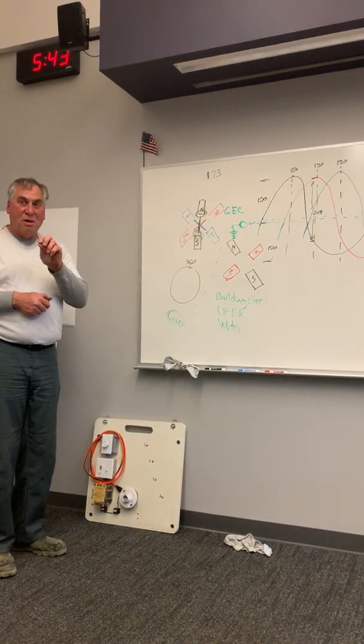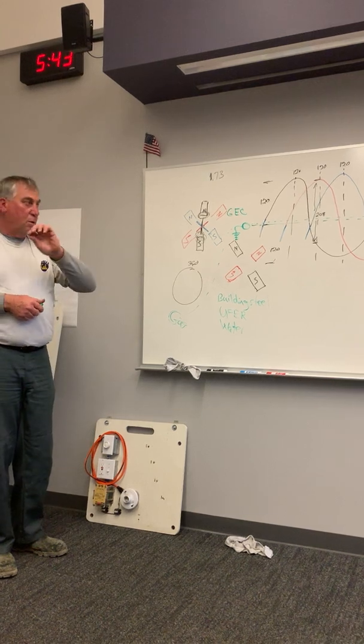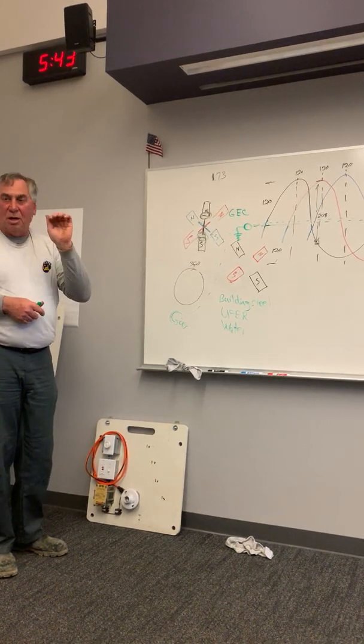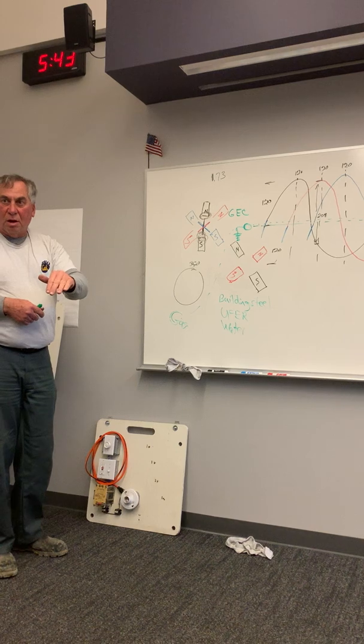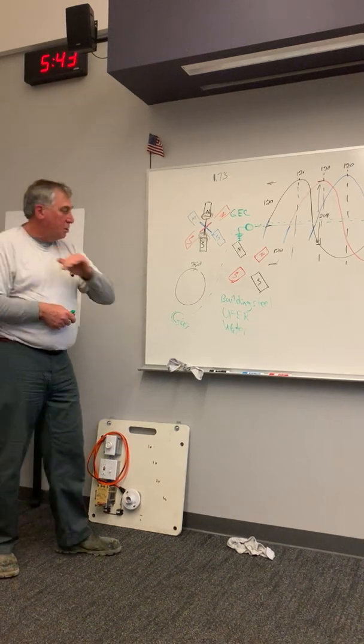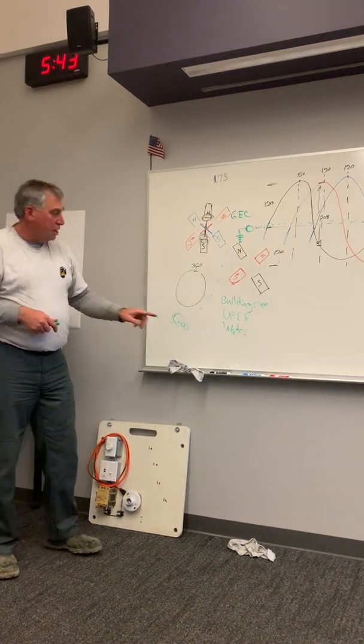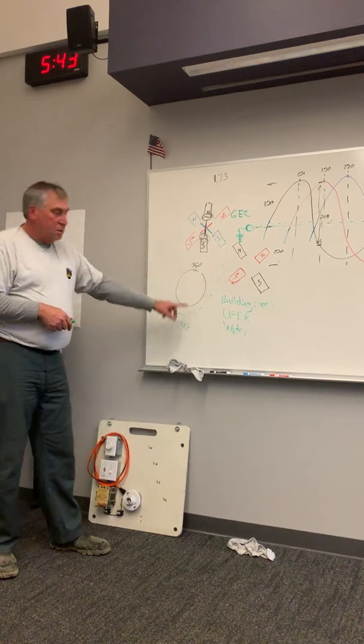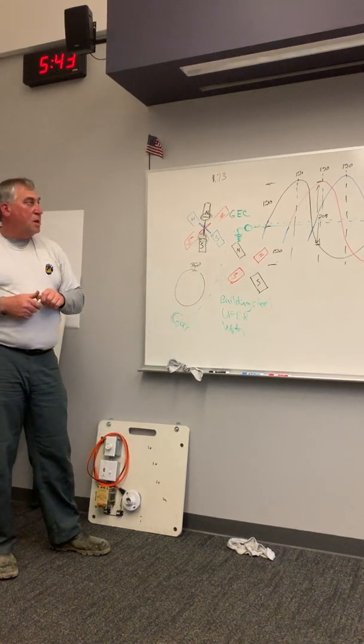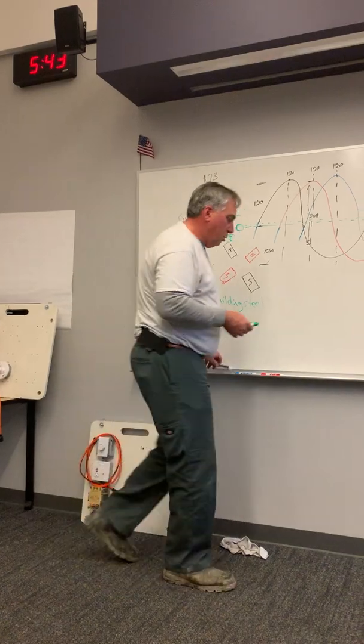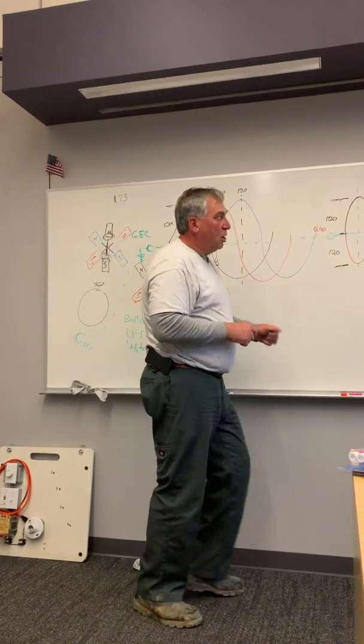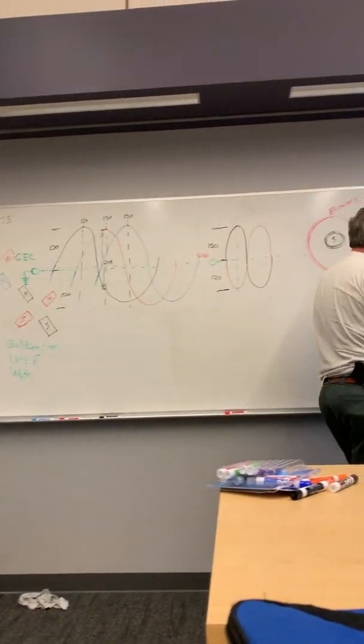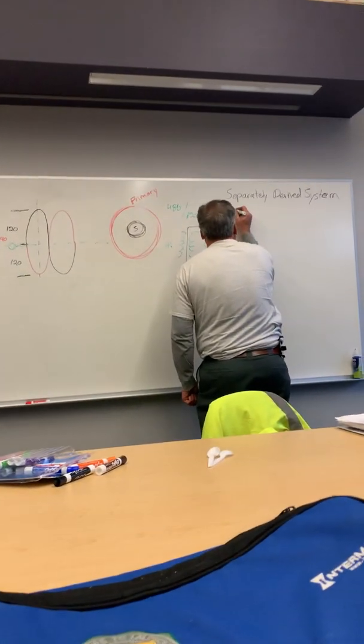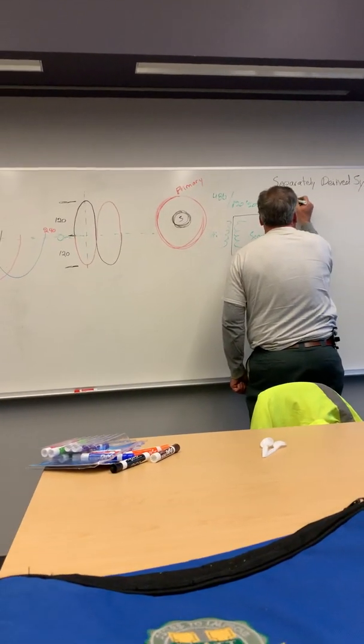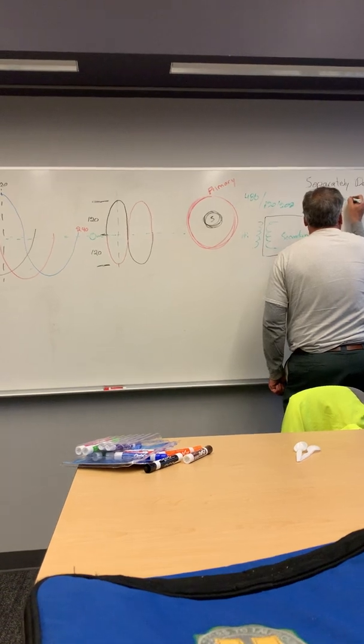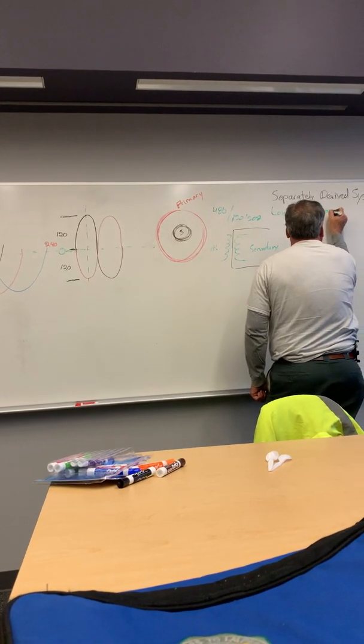Now if anything happens where a wire gets onto a plumbing pipe, it's going to go right back and bond, because it's tied to the cold water, and it's going to come back through. What we really want to do anytime we're doing any grounding at all is make sure we keep a low impedance path to ground.